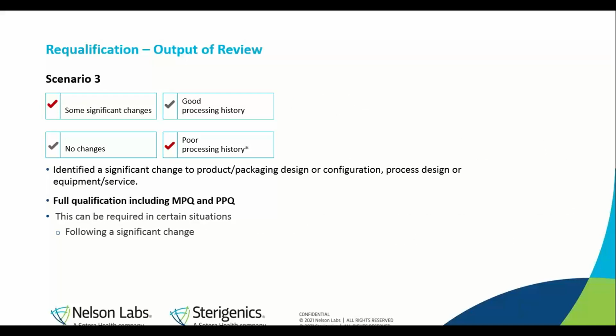Finally, we'll go into a third example, a third scenario. If during the review you've identified some significant changes and there is a good processing history, or you've identified that there are no changes, but there's a very poor processing history, this might have identified a significant change to the product packaging design or configuration, the process design, or even the equipment or service. In this scenario, it would be our worst case scenario because we'd have to perform a full qualification, including an MPQ and PPQ. In other words, going back to the drawing board to start the validation again.